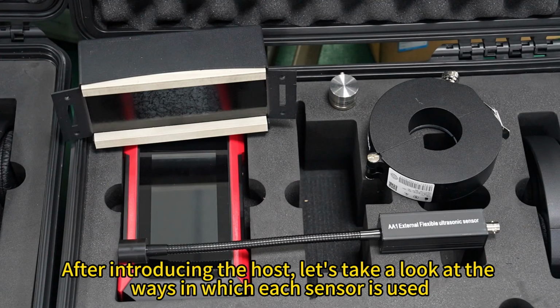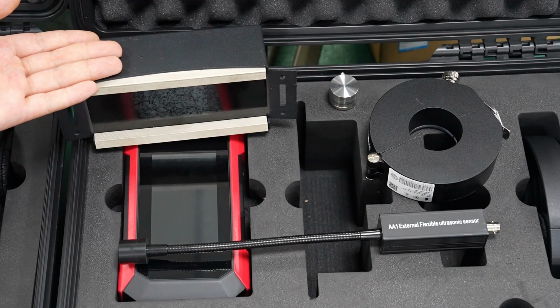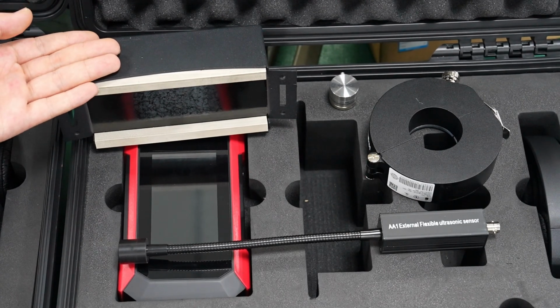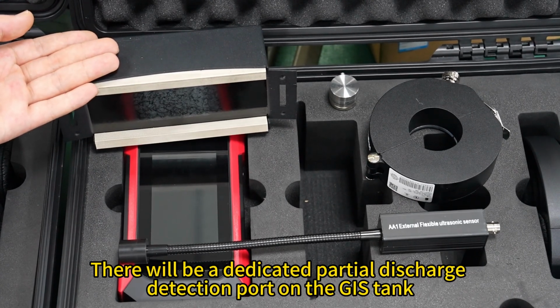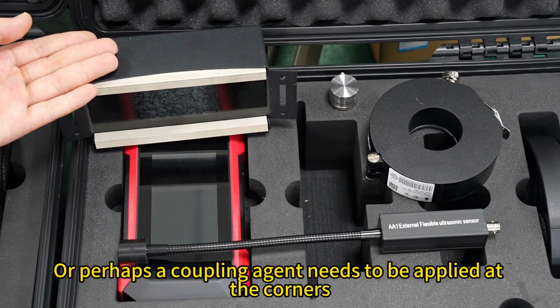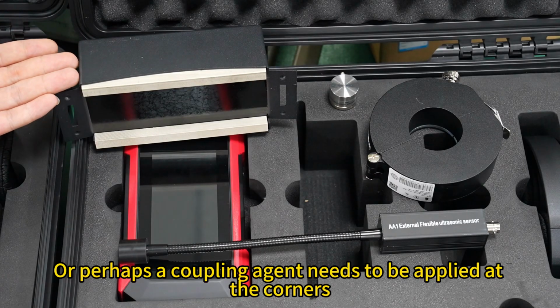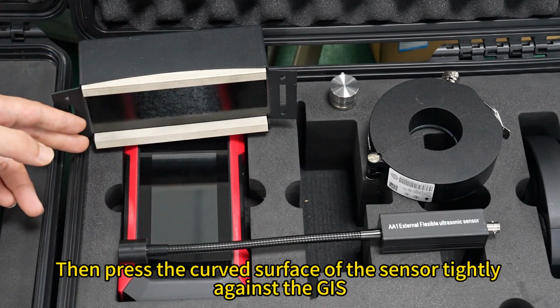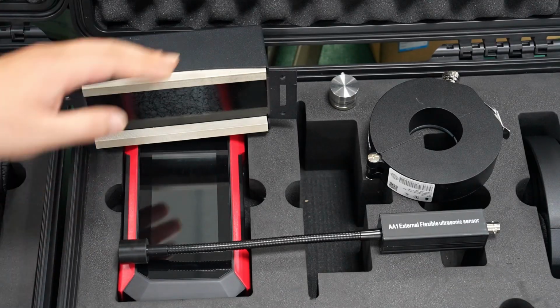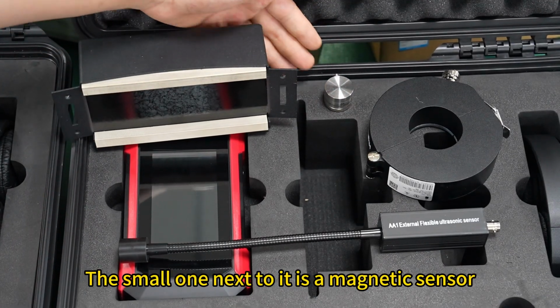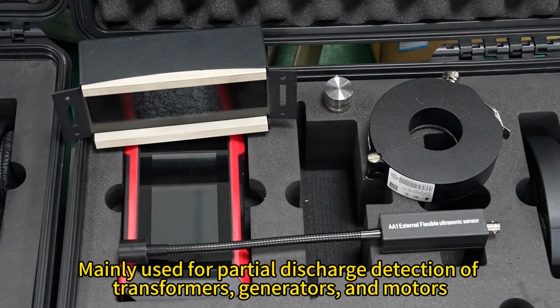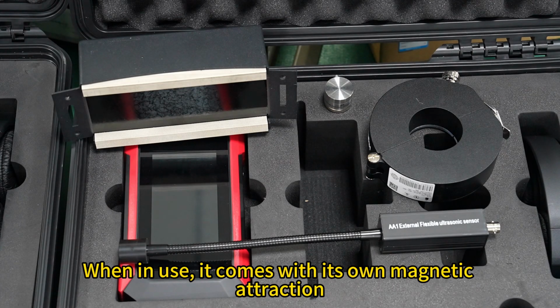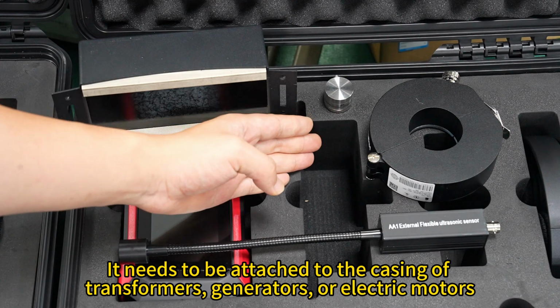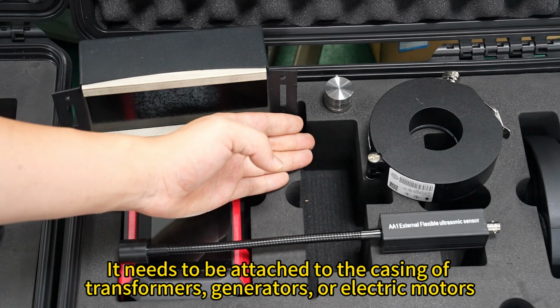After introducing the host, let's take a look at the ways in which each sensor is used. Firstly, this biggest sensor is for testing the GIS. There will be a dedicated partial discharge detection port on the GIS tank, or perhaps a coupling agent needs to be applied at the corners. Then press the curved surface of the sensor tightly against the GIS. The small one next to it is a magnetic sensor, mainly used for partial discharge detection of transformers, generators, and motors. When in use, it comes with its own magnetic attraction. It needs to be attached to the casing of transformers, generators, or electric motors.